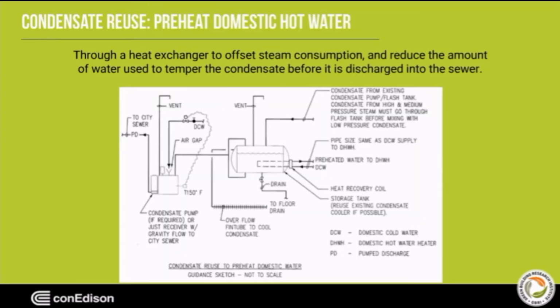Now let's take a look regarding condensate reuse. As steam cools, it changes state from vapor to liquid. This liquid water is called condensate. Automatic valves called traps remove the condensate and help ensure safety and prevent erosion of pipes and other equipment. But if your building wants to be more energy efficient, this condensate can be reused. One way is to use it to preheat domestic hot water. Condensate can be used to preheat domestic hot water through a heat exchanger.